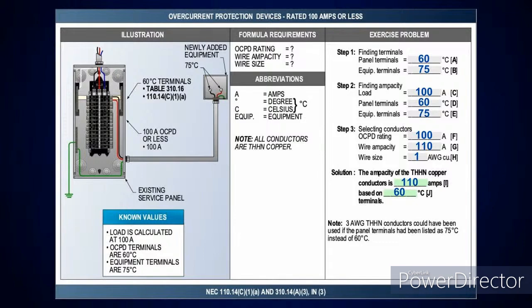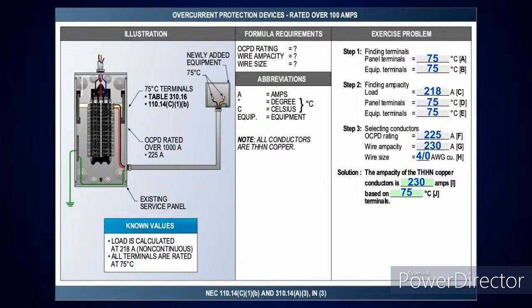Now, just to give you a little bonus thing, James, for a lot of people out there to know, a lot of people think there are breaker terminals that are 60 degrees C. Pretty much the standard across the board when it comes to breakers and equipment is going to be 75 degrees C or larger. So the only time you're going to use that 60 degrees C for 110.14(C)(1) is if the terminals are unknown. James is giving you an example where the terminals are known, and that's where you get those values from. This is the type of thing they could ask you on the test. Yeah, I agree, but you would default to 110.14(C)(1) if the terminals are unknown. That would be (C)(1)(a), the 60 degree, and (C)(1)(b) would be 75 degrees C. Okay? Right.